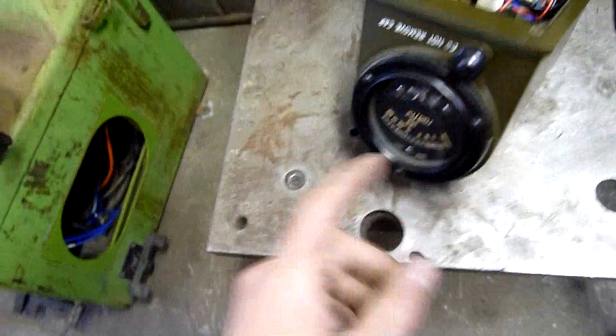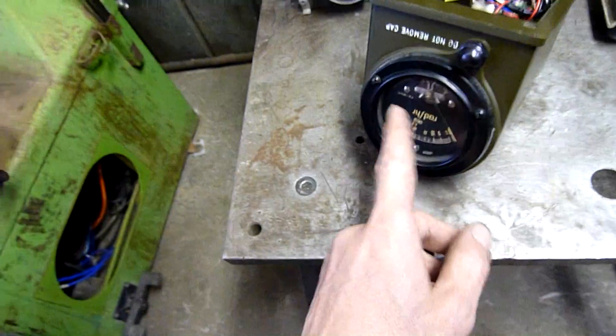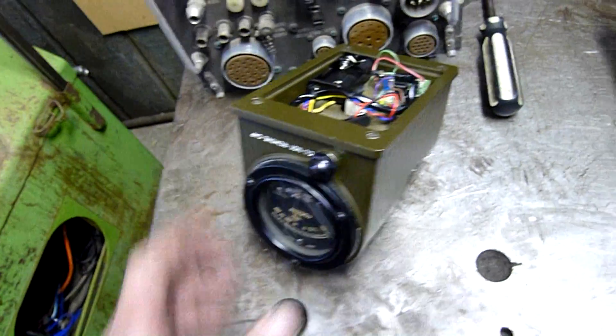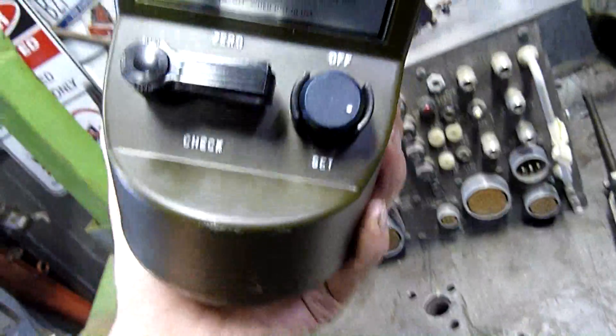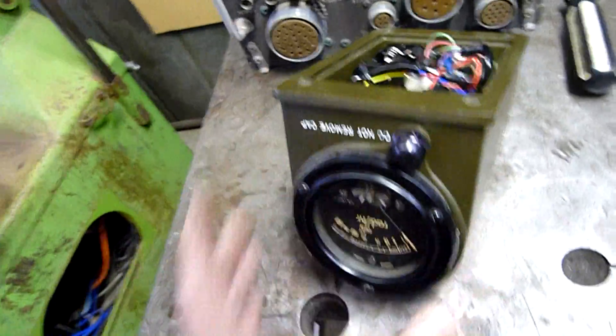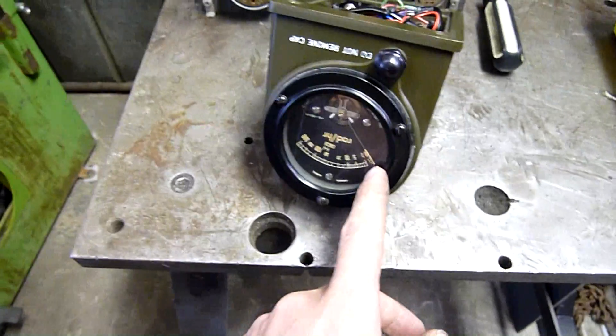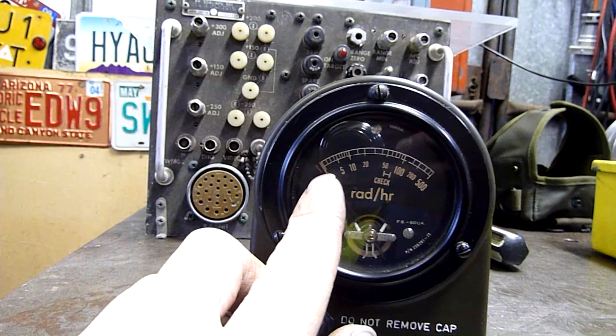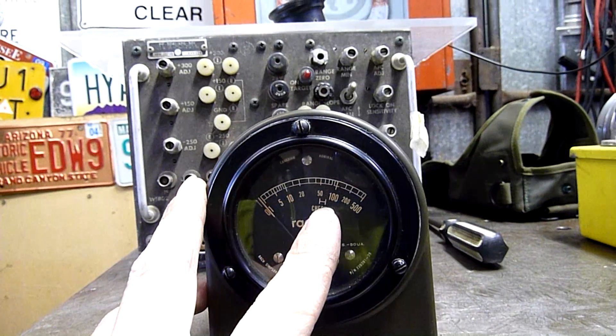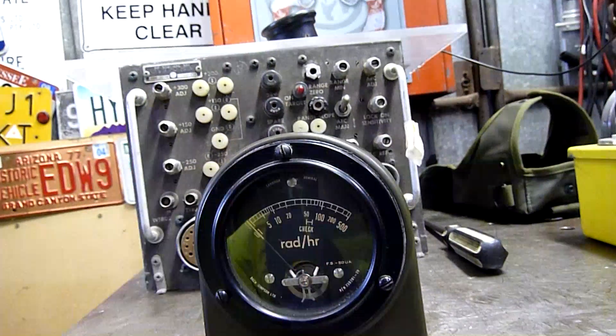I've had this thing powered on a few times. You can flip it over to check and then the needle will move all the way to the check position and stay there indicating that it's actually accurate and calibrated. There's also a set switch there which you can use to zero it. So you turn it on, adjust the set switch until the needle is actually on zero.